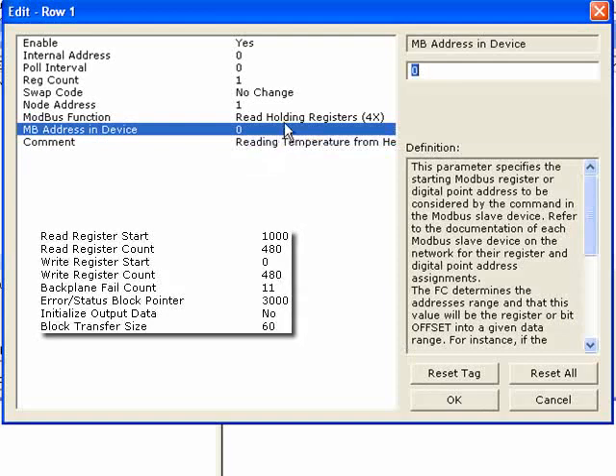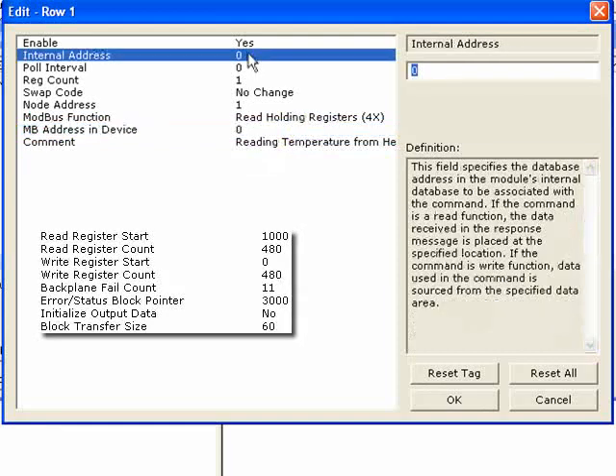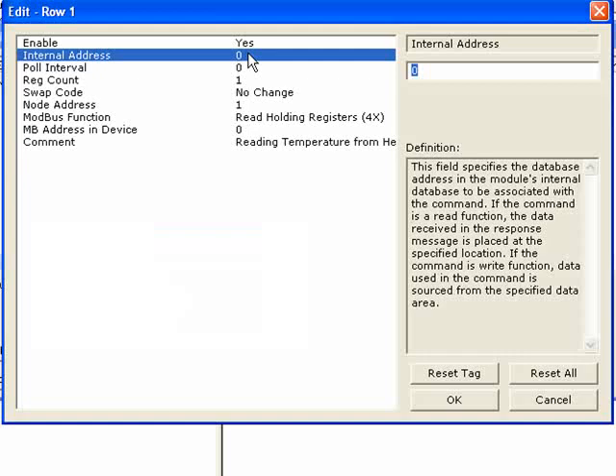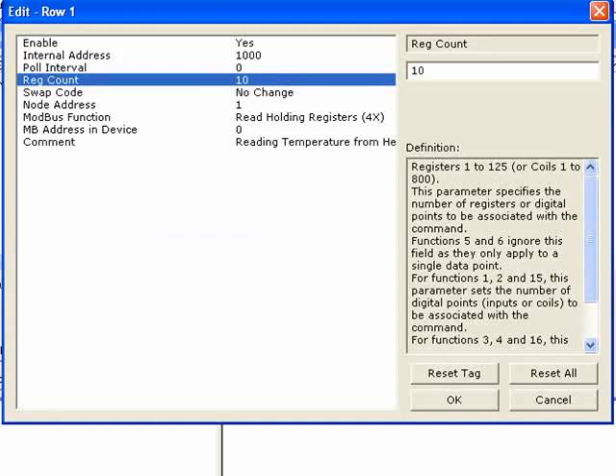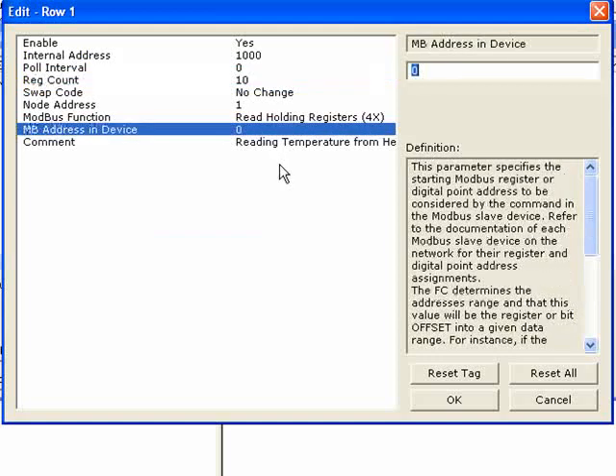In our database setup, we specified that read registers start at address 1,000 to 1,479 — 480 registers. Right now the internal address is set at 0, but 0 to 479 is used for write data. Since this is a read command, I need to set that address to at least 1,000, so I'll set it to 1,000. I'll change my count to 10, meaning I want to read 10 registers. I'll leave Modbus Address in Device at 0, which corresponds to register 40001. Then I'll click OK.